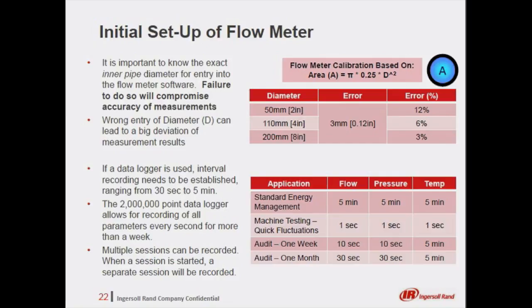Okay, as David mentioned, we'll discuss some installation tips that you might need to be aware of when speccing out a flow meter. Paying careful attention to the initial setup of each flow meter is critical to ensuring accurate readout of system measurements. Knowing the exact inner pipe diameter for input into the Airscout Studio will drive this accuracy.